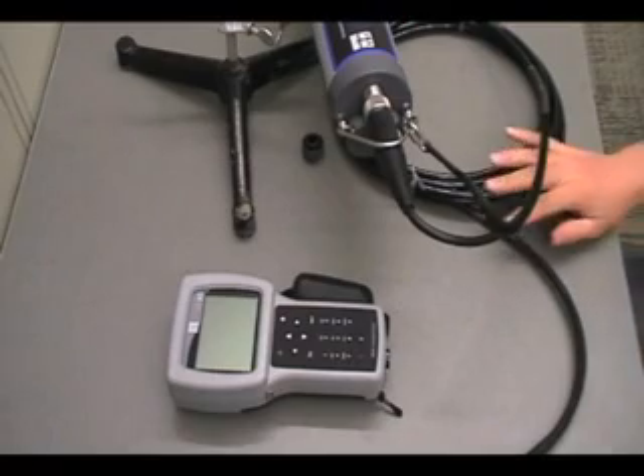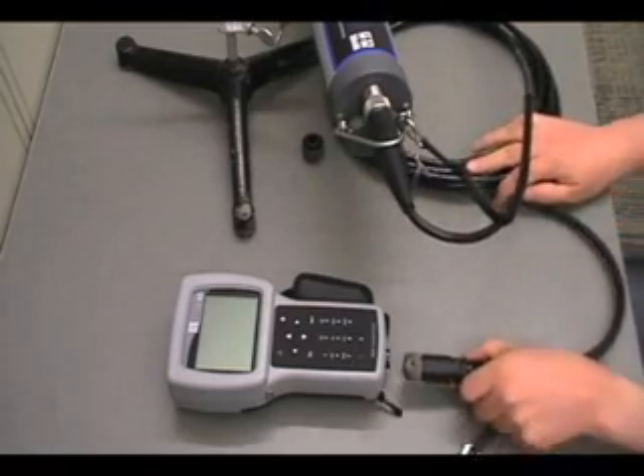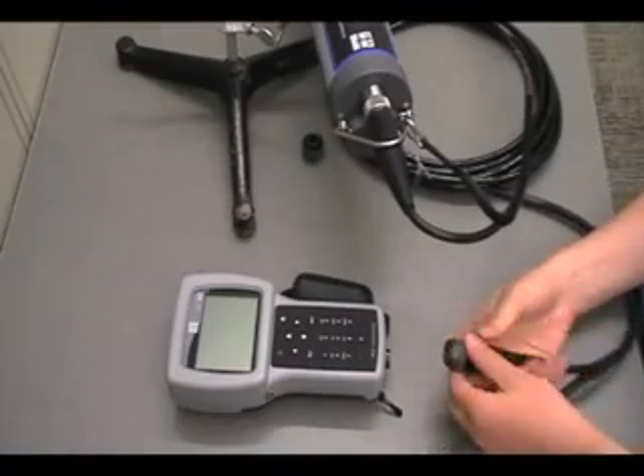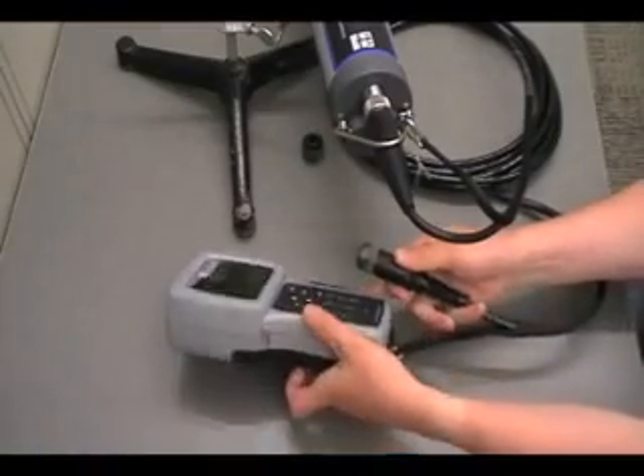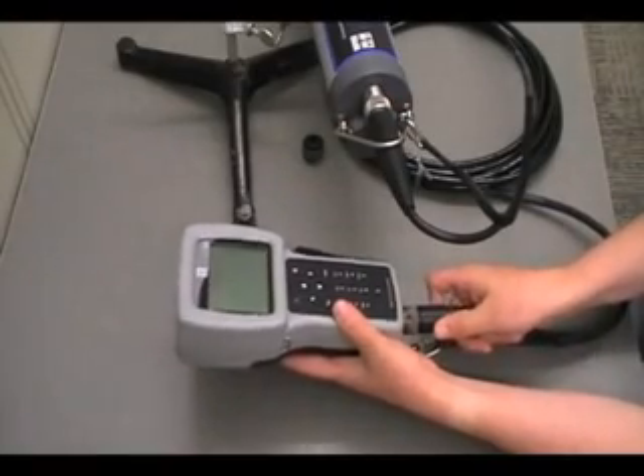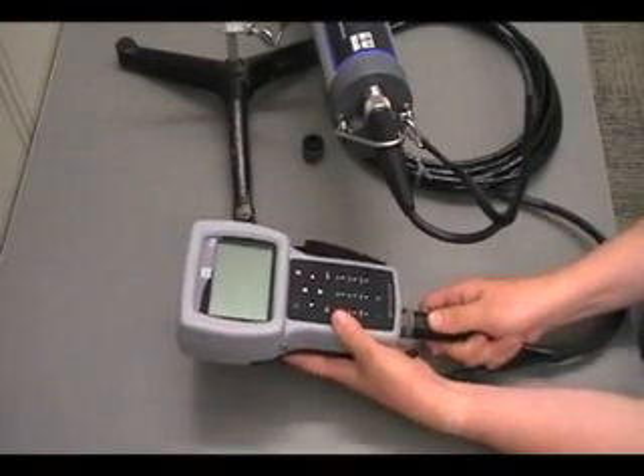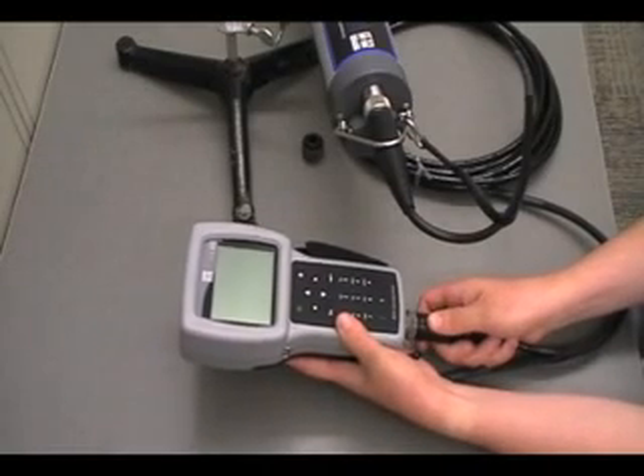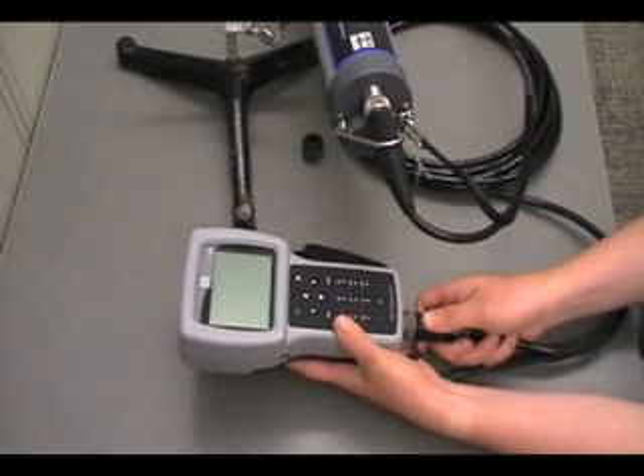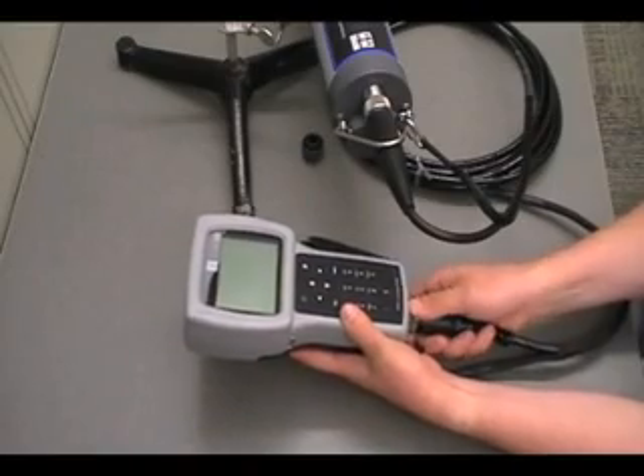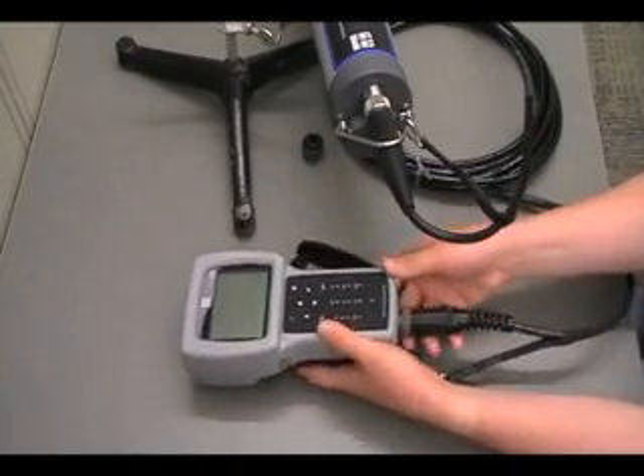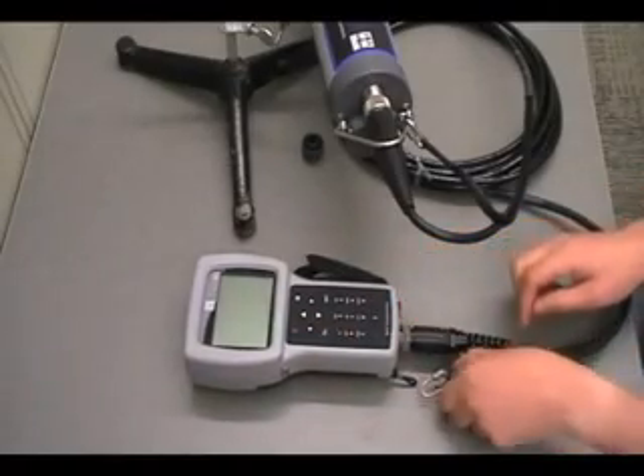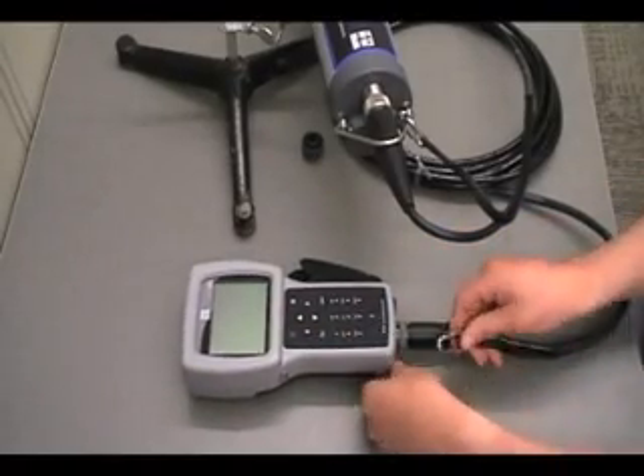Step 5. At its other end, the field cable plugs directly into the 650 display module using an 8-pin connector. Line up the guides and pins inside the connector. Be careful not to cross-thread. Gently turn the nut clockwise until it clicks to lock the connector in place. Attach the second strain relief connector to the display unit.